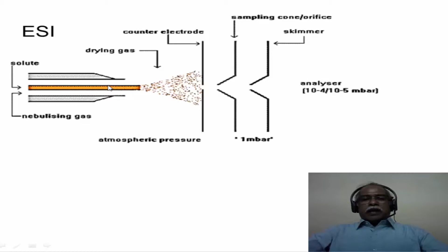And during the course of the fine spray, there is also a nebulizing gas which is passed through the sample. This is better represented in the next slide. You can see here there are coaxial tubes that are placed. In the central tube, the analyte solution is injected, and in the surrounding tube, the nebulizing gas, which is typically dry nitrogen gas, is passed through. In the fine spray that is produced here, the droplets are formed, and because of the nebulizing gas, the droplets undergo slow evaporation of the solvent until the solvent molecules are completely evaporated and only the solute molecule in the gas phase is obtained.